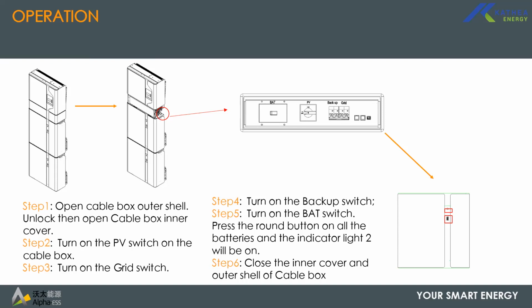After the battery breaker, on the physical battery, there is a small switch just above the battery bar indicator. Just push it in, and then the battery would come on. The battery status indicator would come on and flicker to show that the batteries are connected. If the battery is initializing, the outer ring would flicker at faster intervals, once every second. And once the BMS has done the checks and is communicating with the inverter properly, the outer ring would flicker after about 10 seconds to show that the battery is ready and on standby. So that's the backup procedure.